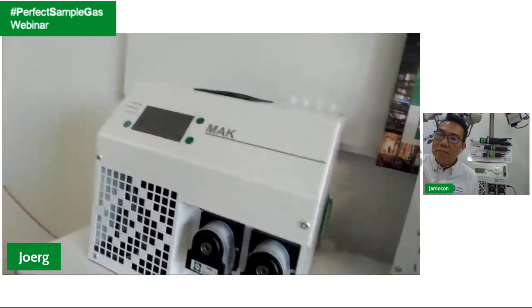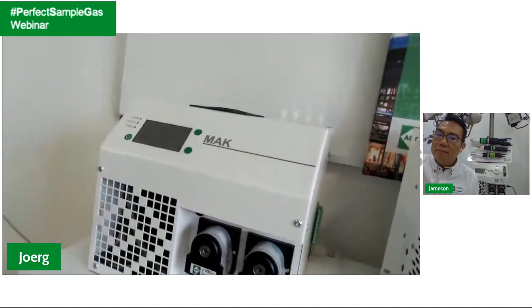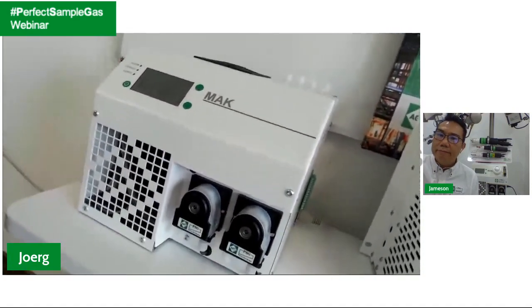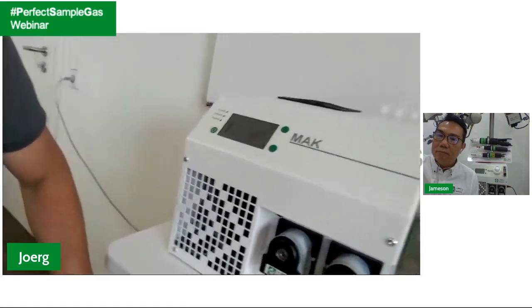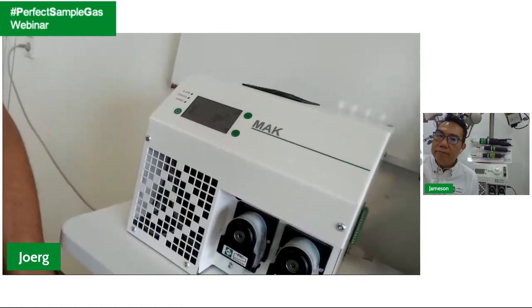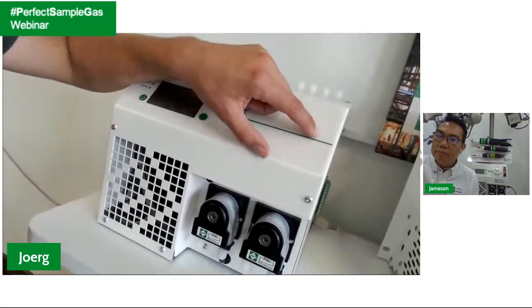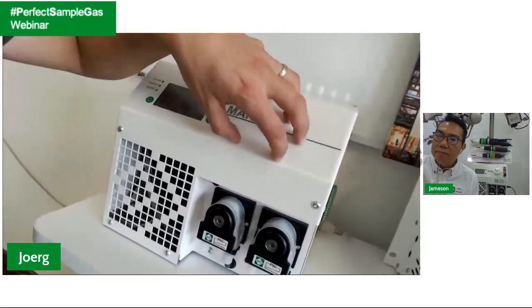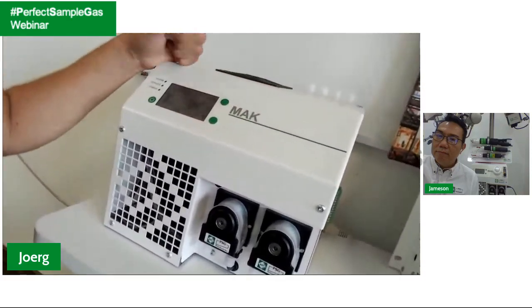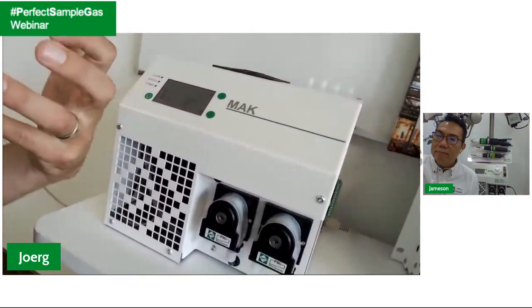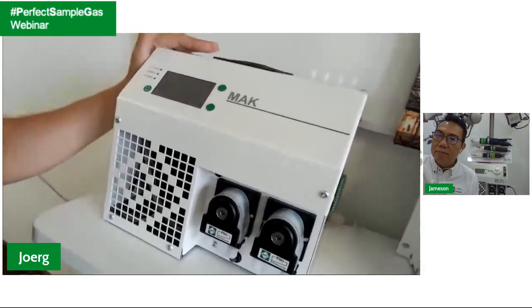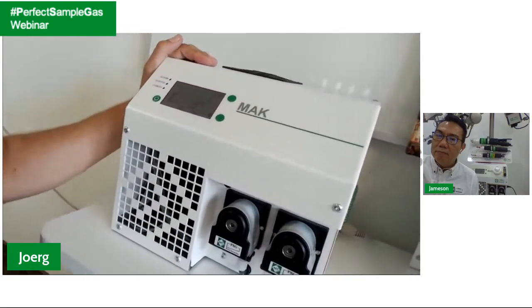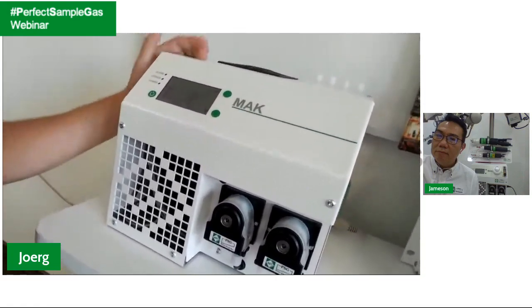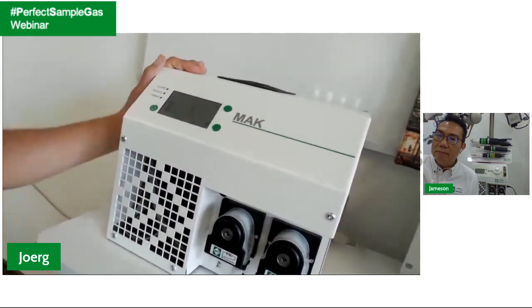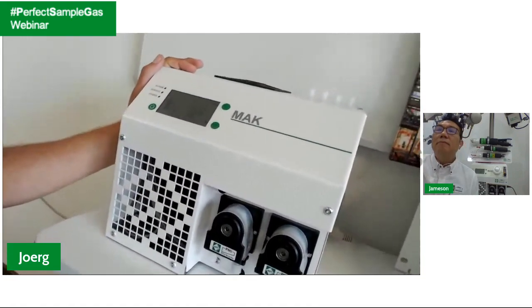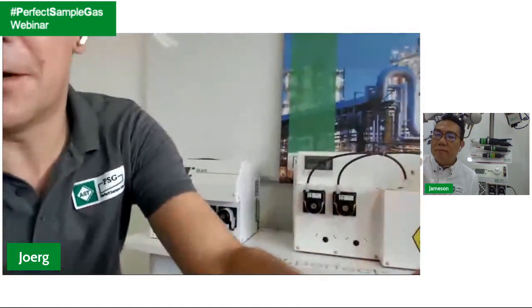One big advantage is, and I'd like to invite you to use this opportunity, in the MAK20 we are capable of integrating a gas sampling pump, a flow meter, a depth filter. So there are many options, and when you contact us regarding your sample handling system, Jameson can help you find the perfect sample gas configuration. That's really what I wanted to show.